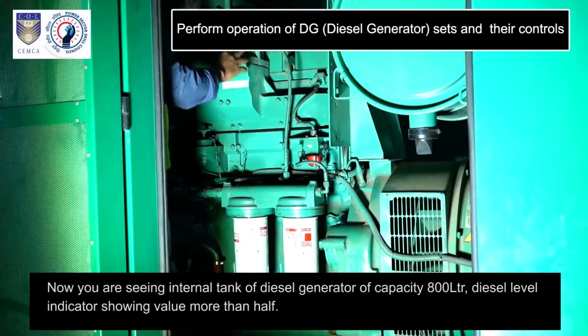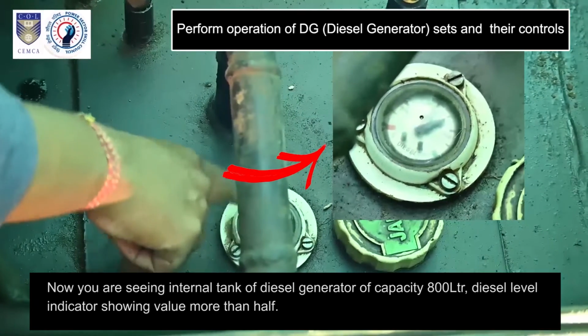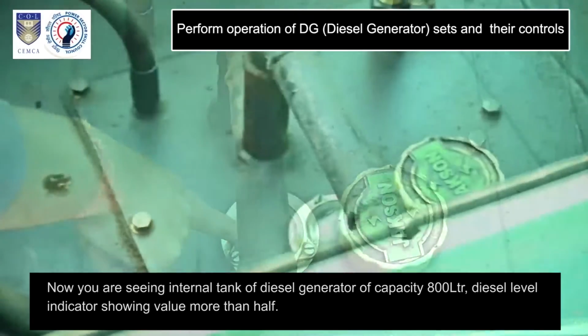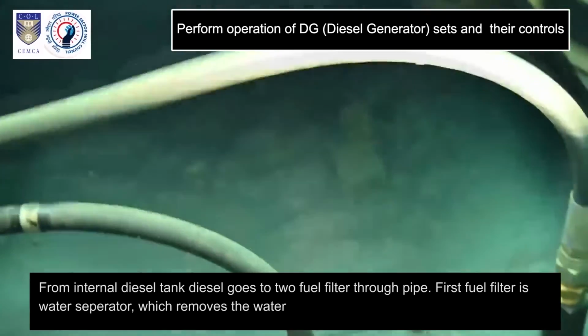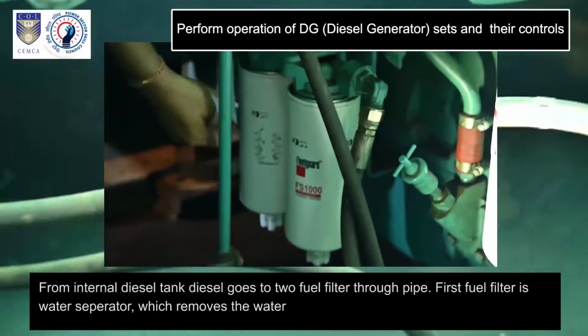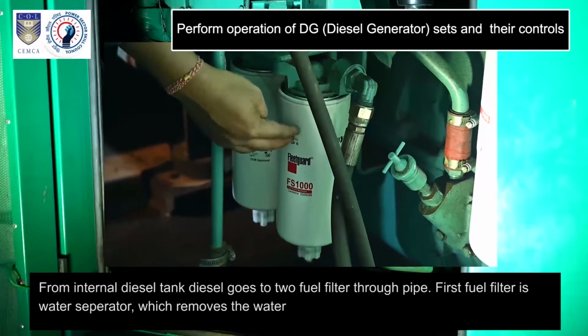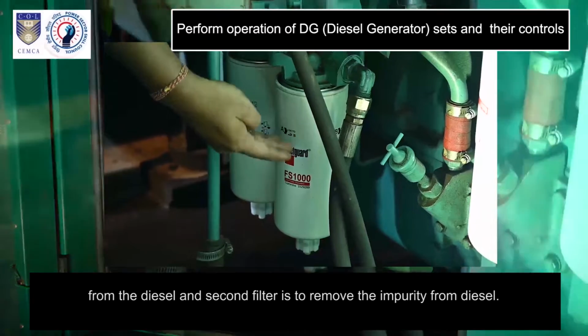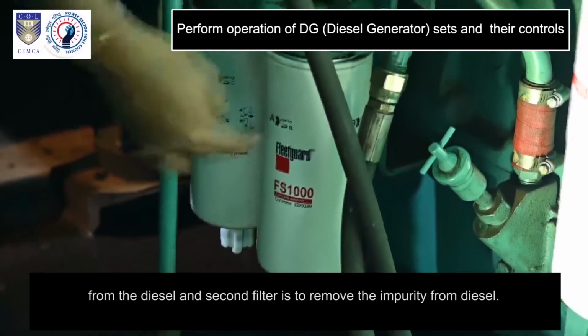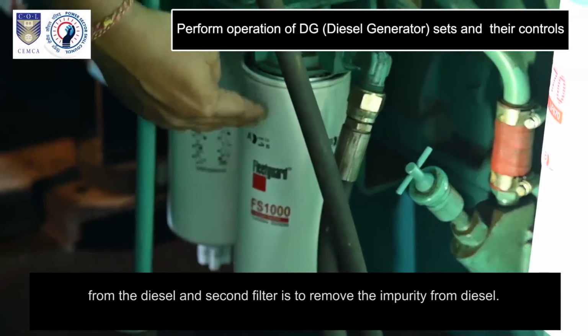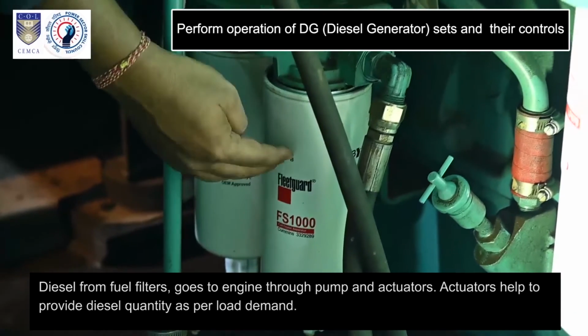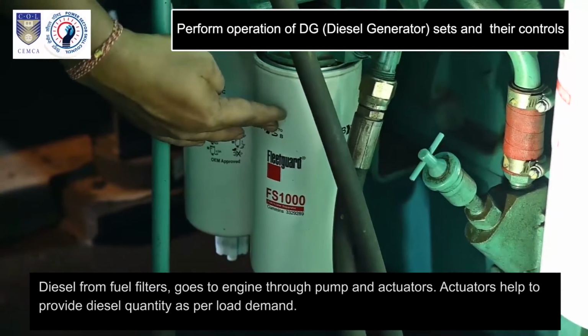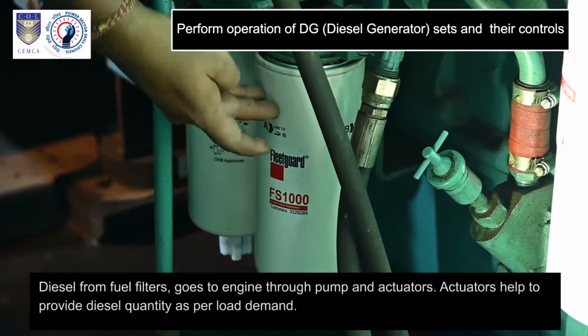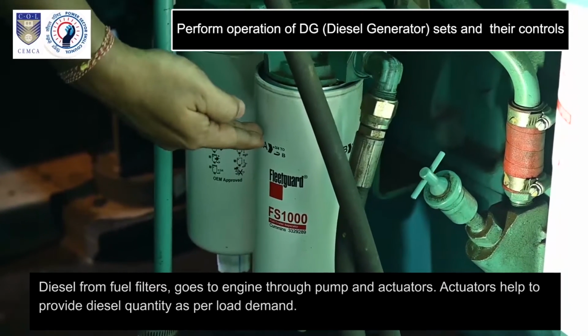Now you are seeing the internal tank of the diesel generator of capacity 800 liters. The diesel level indicator is showing a value more than half. From the internal diesel tank, diesel goes to 2 fuel filters through a pipe. The first fuel filter is a water separator, which removes the water from the diesel, and the second filter is to remove the impurity from diesel. Diesel from the fuel filters goes to the engine through a pump and actuators. Actuators help to provide diesel quantity as per load demand.